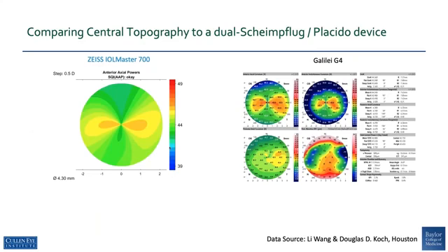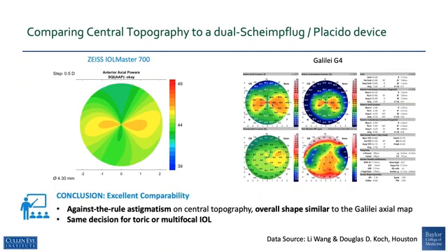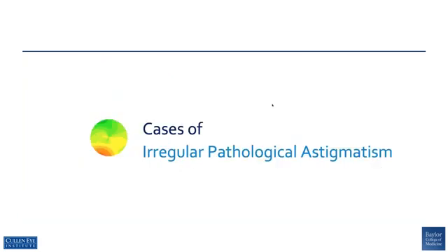Here is a comparison of central topography to the Galilei with against-the-rule astigmatism. In the central topography on the left you can see against-the-rule astigmatism, which is also seen on the Galilei map, showing excellent comparability. The overall shape is similar to the Galilei, and again I believe the clinician would make the same decision for a toric or multifocal IOL.